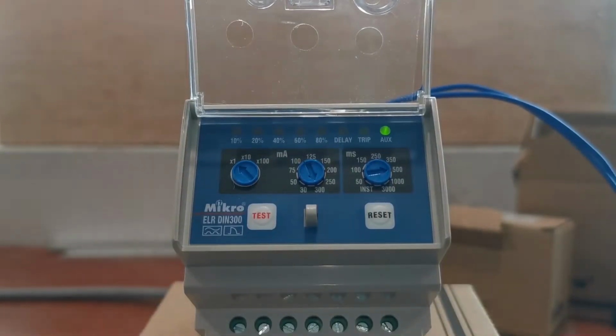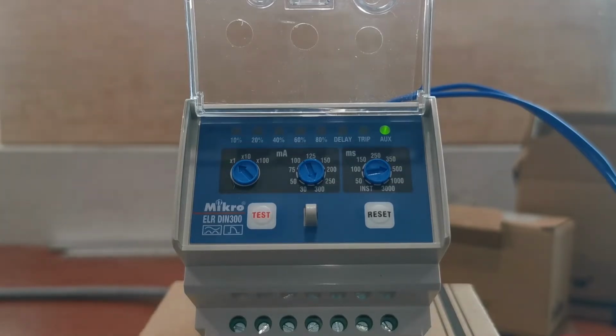Hi, today we're going to introduce our DIN300 earth leakage relay by Mikro. This is a type A earth leakage relay. This earth leakage relay can detect a sinusoidal leakage current, a half bridge rectified leakage current, and also a pulsating leakage current. Mikro's ELR range is compatible only with Mikro's ZCT, zero sequence current transformer.